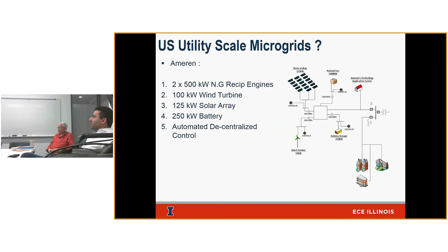So sizing the microgrid depends on your objective. Our objective was to support these 200 customers feeding through the substation. The first thing you do is figure out your load requirement. This is a 1-year load profile for that customer - the 200 customers - and that's what their load profile looks like. It peaks in the summer, so this is a summer peaking circuit.